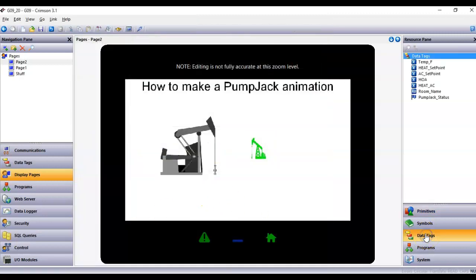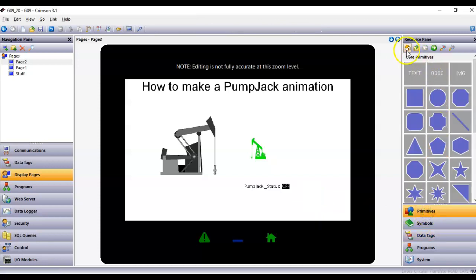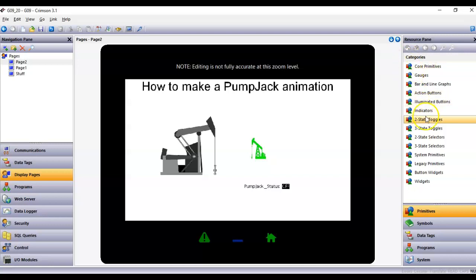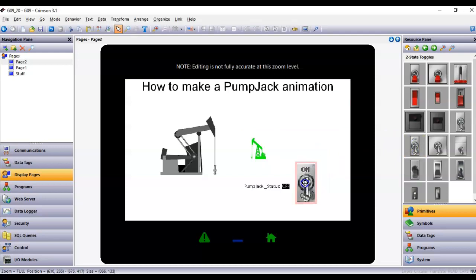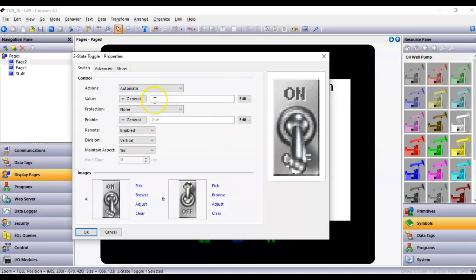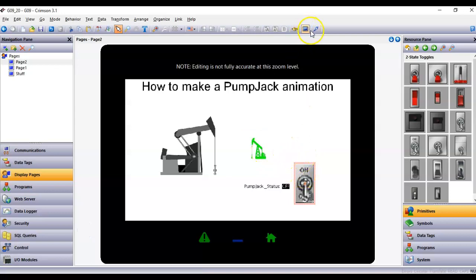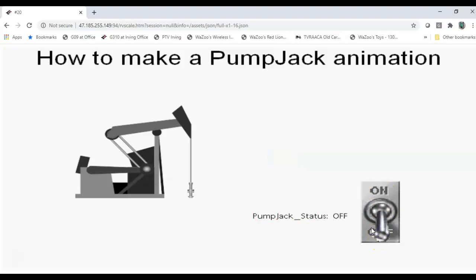I'll grab a toggle button from Symbols under Two State Toggles — a standard simple toggle button — make it a little bigger and place it on screen. I'll double-click it and use the pump_jack_status tag for control. Under Data Tags I'll drag that tag right in. Now according to that expression, the animated image will only show up when the tag is on. Testing: you don't see the pump jack when it's off; turn it on — there it is running; turn it off — it stops. That works great.